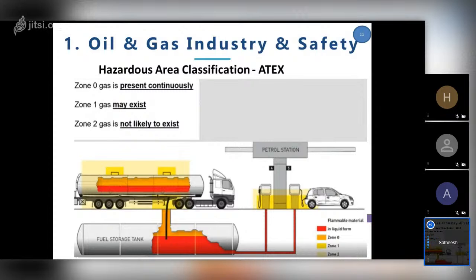In the plant, you need to know how all the areas are classified and what equipment to use. As an instrumentation professional, we need to select instruments accordingly and ensure compliance. Each instrument is different—for example, zone 1 certified equipment is much better than zone 2 certified equipment, and zone 1 equipment cannot be used in zone 0. Zone 0 equipment can be used in all areas, because that is the safest equipment or instrument.